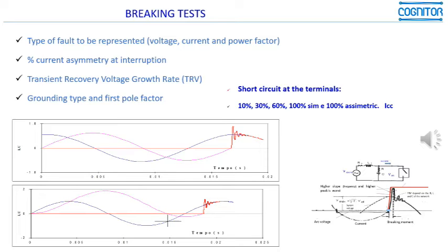In the beginning of a substation, when it is new, normally the circuits are not completely developed, the loads are not completely implanted near the substation, and you may have the circuit breaker operating at 10%, 30% of the maximum possibilities that it has.